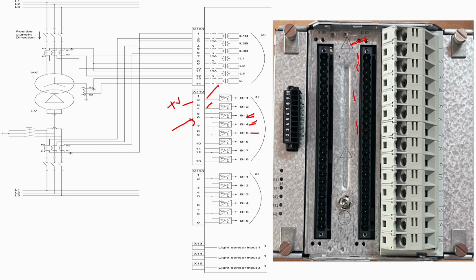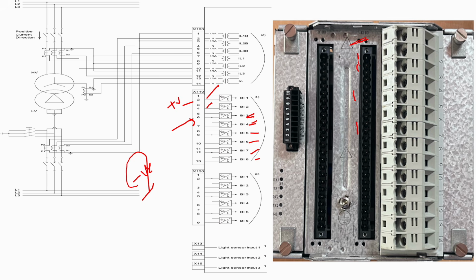Likewise, BI5 and BI6 are also not individual. They also have their common negatives. Likewise, 7 and 8 as well. So for LBB protection, whenever you require a separate negative, like LBB protections, in that case you require an individual negative. You cannot connect the LBB negative with other protections, because sometimes our special protections have individual positive and negative. Okay, so for that reason we should not connect.